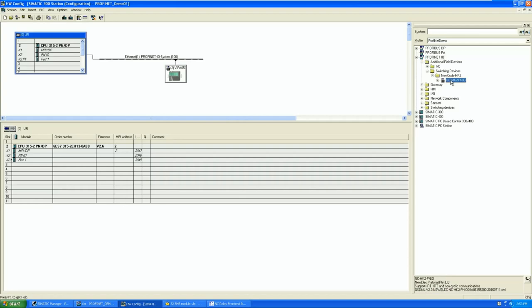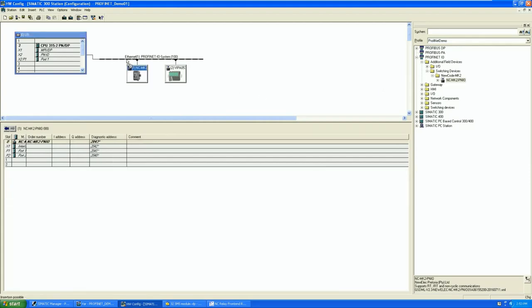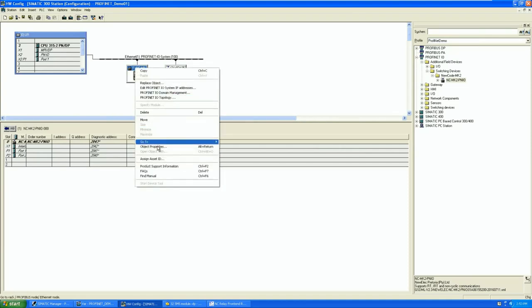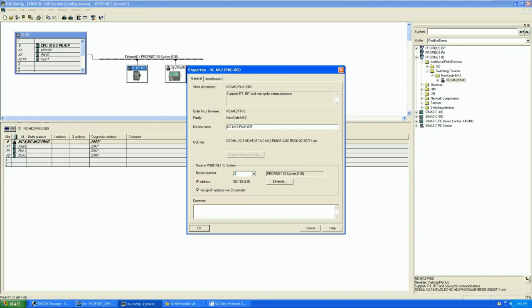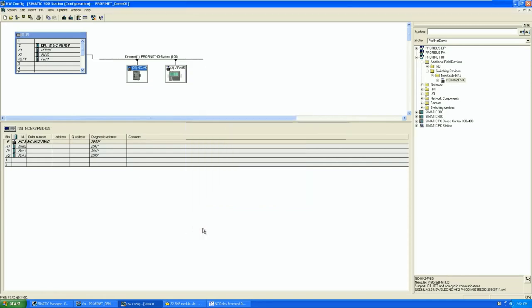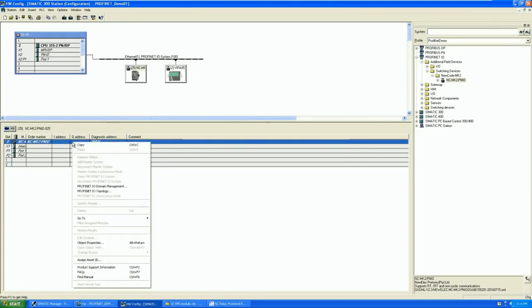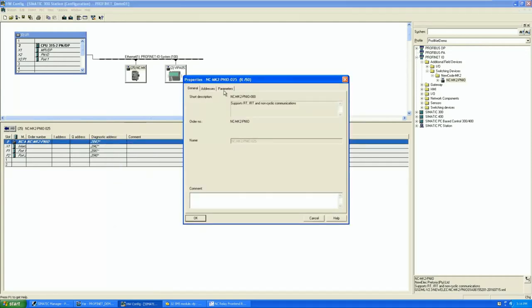As for the setup procedure underneath the PLC, we can go into the hardware config of the PLC. In order to add the NewCode PROFINET slave device, we go underneath PROFINET IO, Additional Field Devices, Switching Devices, NewCode Mark II, and there we can find the NewCode Mark II PROFINET IO. It can be added to the bus by simply dragging and dropping it onto the bus. After this is done, we need to set up what address this slave device is by right clicking, Object Properties, and changing the last two digits of the device name to 25 which our device has been programmed to. Device number must also match this. The Ethernet IP address must also match 25. We also assure that the assigned IP address via the IO controller is also selected. Press OK.